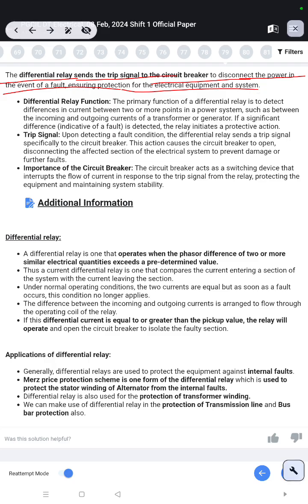Differential relay function. The primary function of a differential relay is to detect differences in the current between two or more points in a power system, such as between the incoming and outgoing currents of a transformer or generator. If a significant difference indicative of a fault is detected, the relay initiates a protective action.